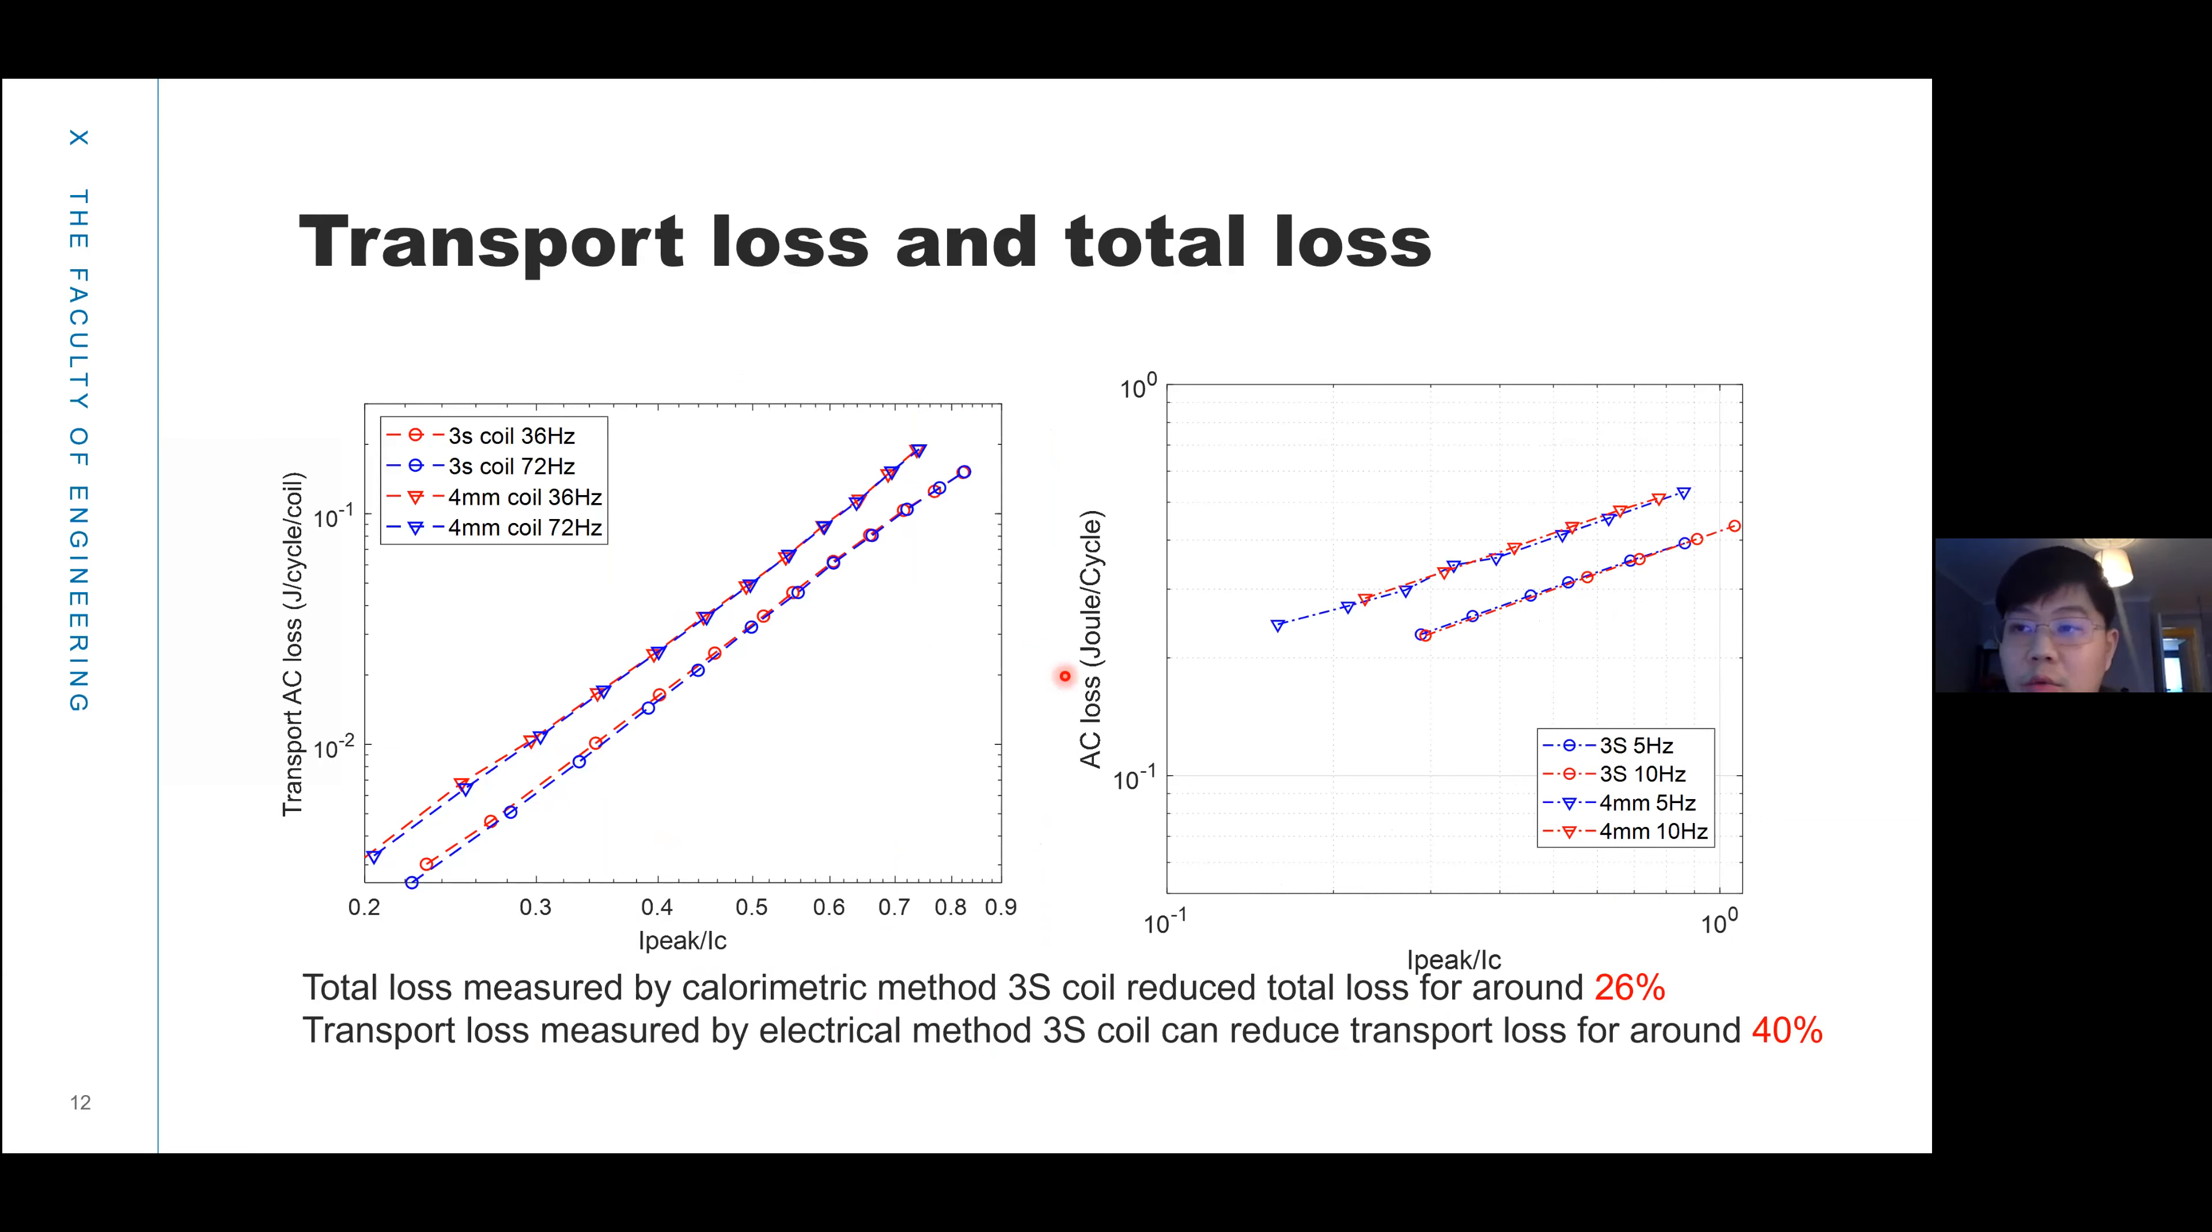We put both coils into the test platform and measured the transport loss and total loss. We found the transport loss, measured at 36 hertz and 72 hertz for both coils, can reduce around 40 percent. We put the coil into the HTS machine platform and ran it at different frequencies and different applied transport currents. We found the total loss of the 3S coil can reduce by around 26 percent.